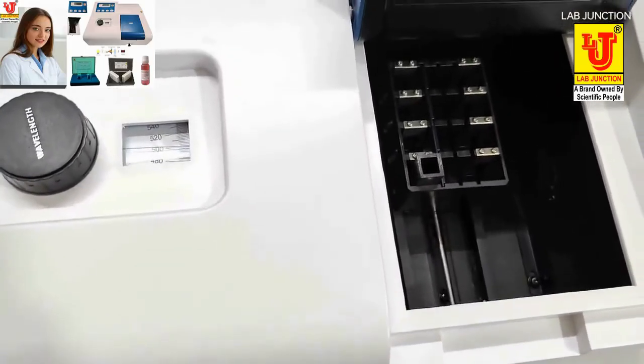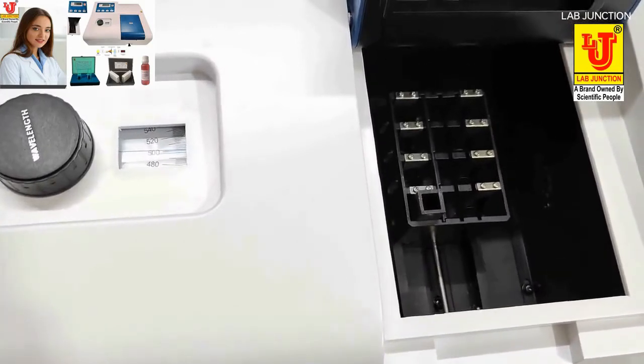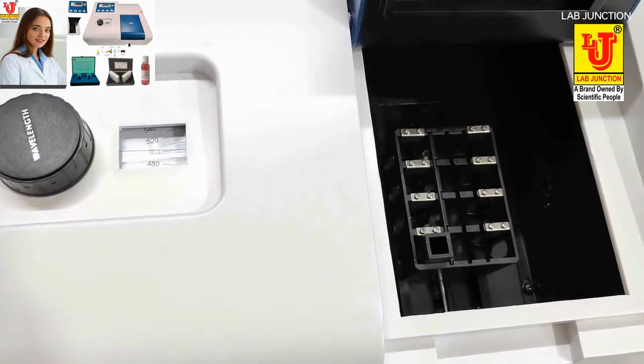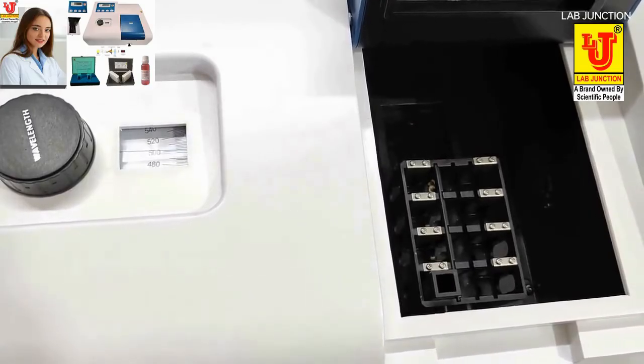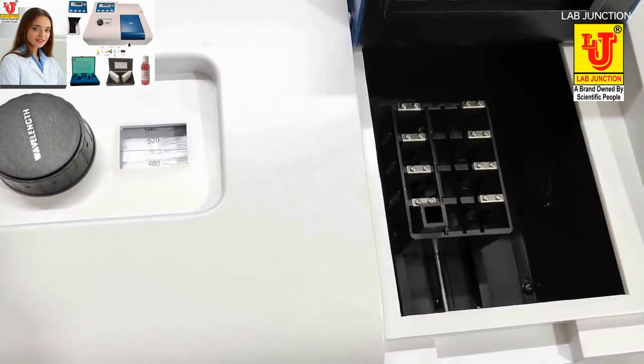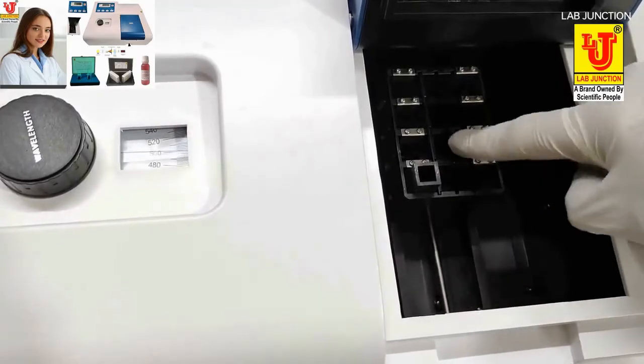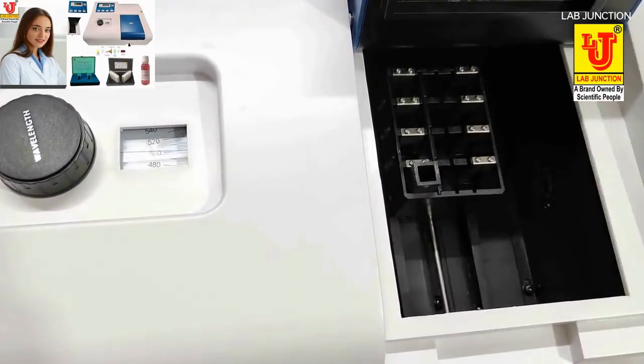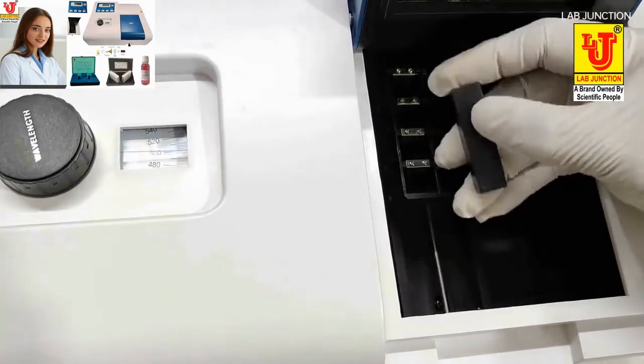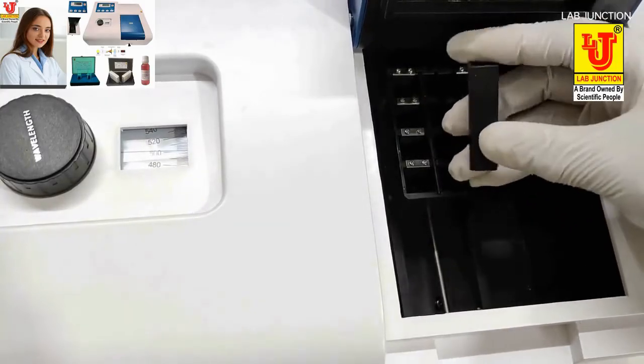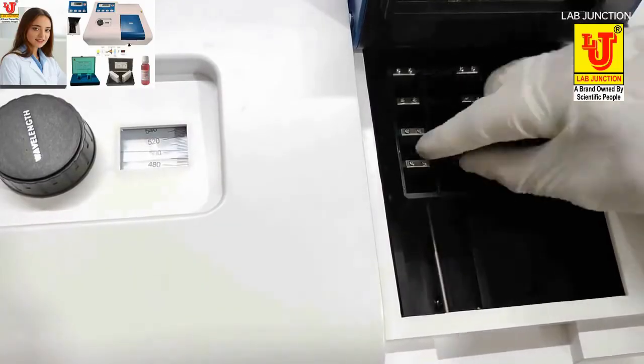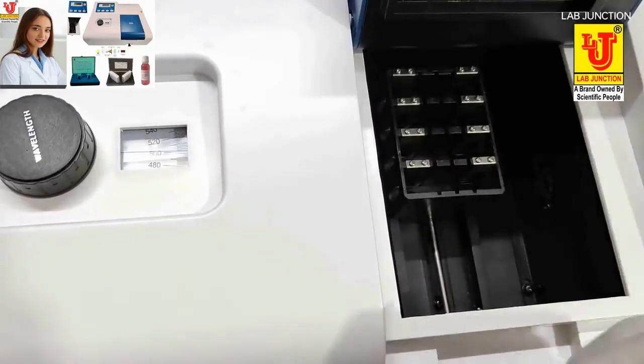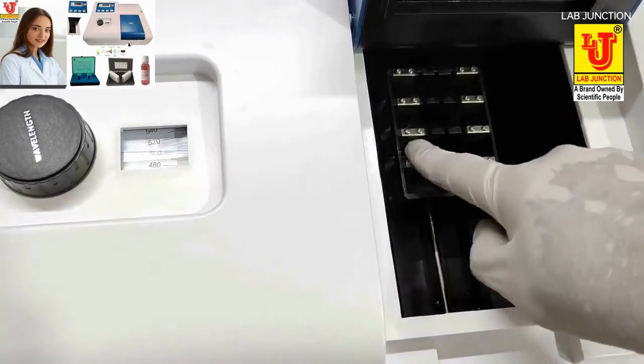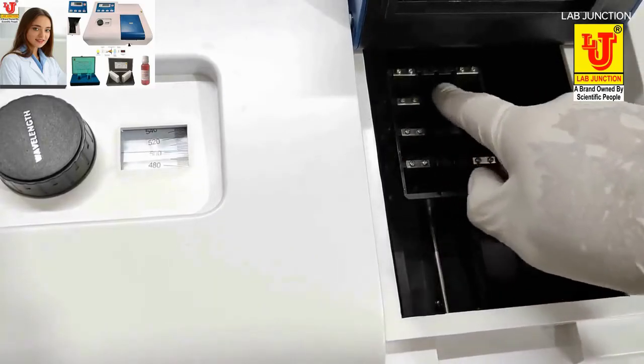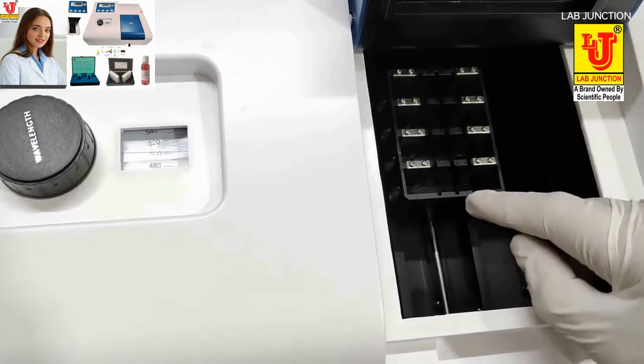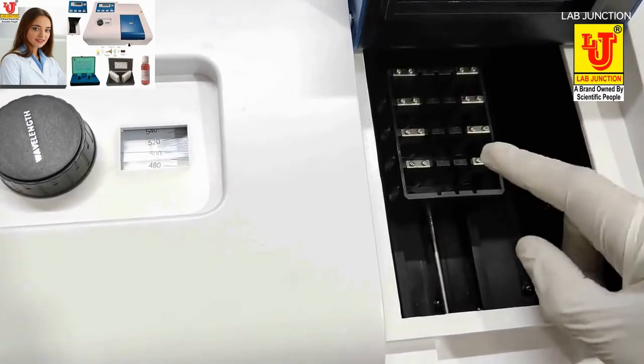Now this is position 1, 2, 3, 4. You can place 4 cuvettes at a time. 1, 2, 3, 4. Now this is the black dummy to set preset 0. If you remove this, you can place 4 50 mm glass cuvettes or 20 mm, 30 mm, 40 mm.